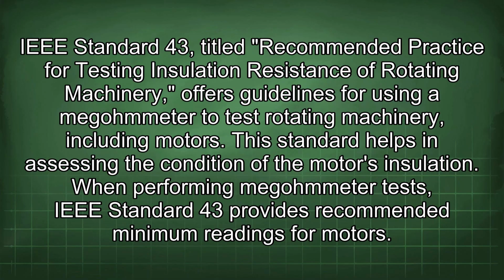IEEE Standard 43, titled Recommended Practice for Testing Insulation Resistance of Rotating Machinery, offers guidelines for using a megohmmeter to test rotating machinery, including motors. This standard helps in assessing the condition of the motor's insulation.